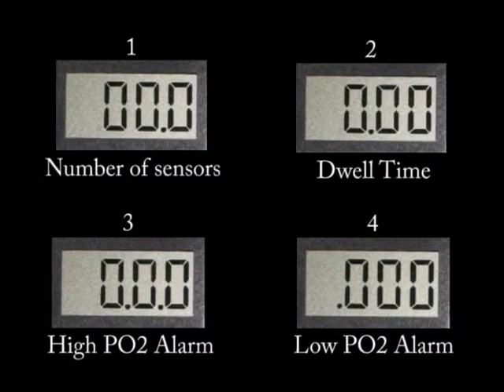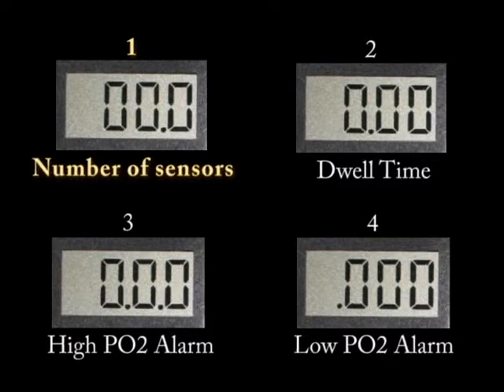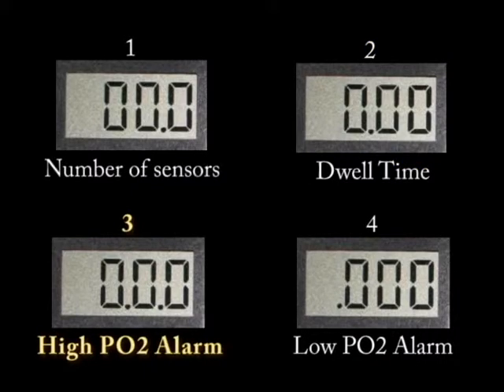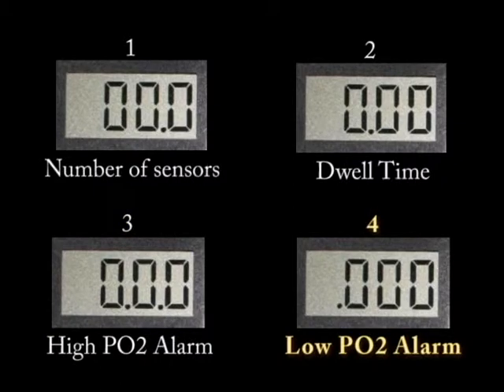Here we see the four steps in the menu system and their associated decimal point position. Step one is changing the number of sensors attached to the display board. Step two is the amount of dwell time between displaying subsequent sensor readings. Step three is the high PO2 alarm set point, and step four is the low PO2 alarm set point. In the future there may be more options, so please refer to your owner's manual.